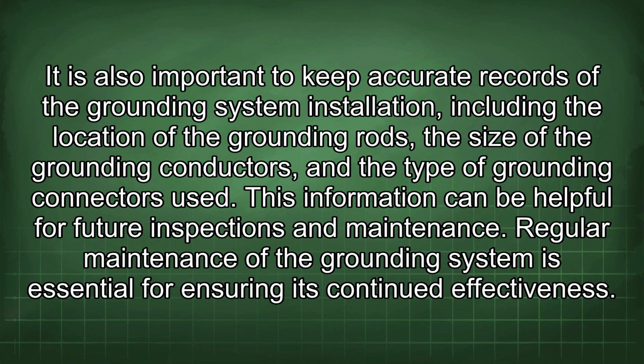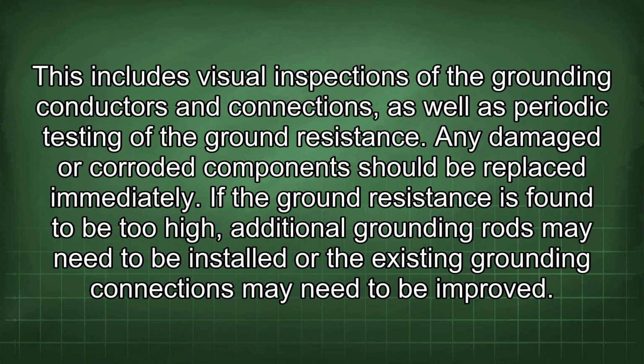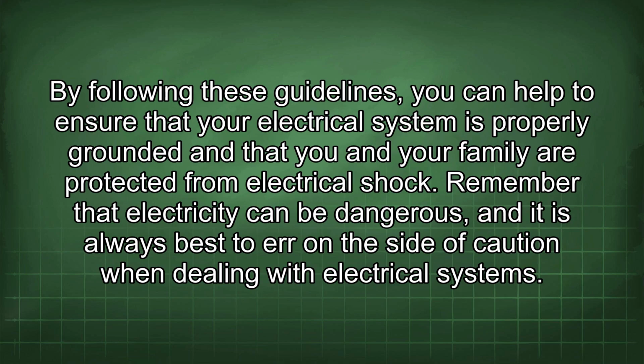Regular maintenance of the grounding system is essential for ensuring its continued effectiveness. This includes visual inspections of the grounding conductors and connections, as well as periodic testing of the ground resistance. Any damaged or corroded component should be replaced immediately. If the ground resistance is found to be too high, additional grounding rods may need to be installed or the existing grounding connections may need to be improved. By following these guidelines, you can help to ensure that your electrical system is properly grounded and that you and your family are protected from electrical shock.